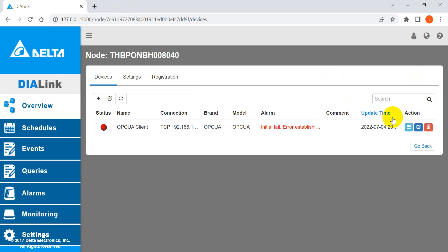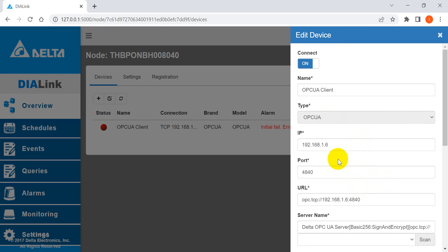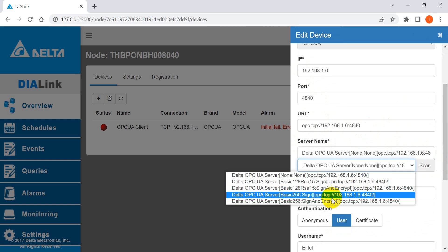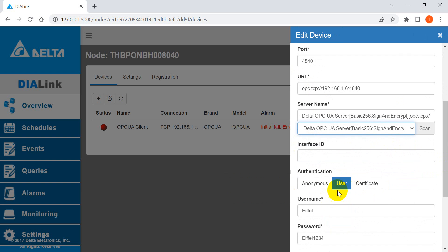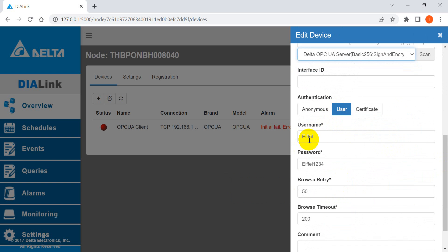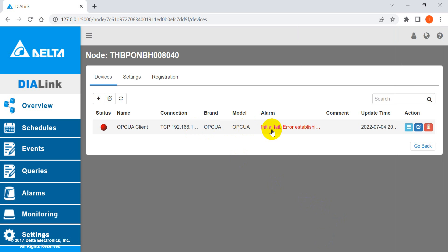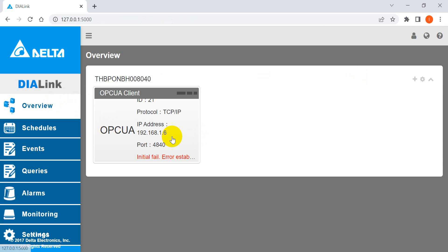In DIALink, click to define the OPC UA type, IP address, and port number, then click Save Change. You will see an 'Initial Fail' message because at this point the server and client do not have each other's trusted certificate yet.